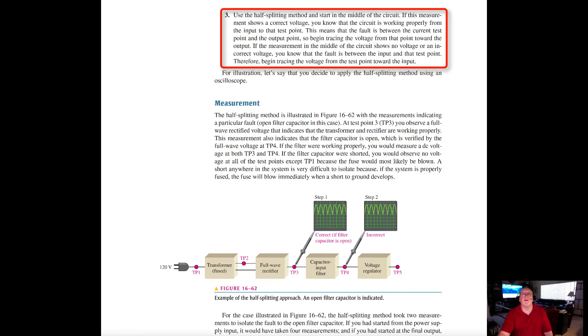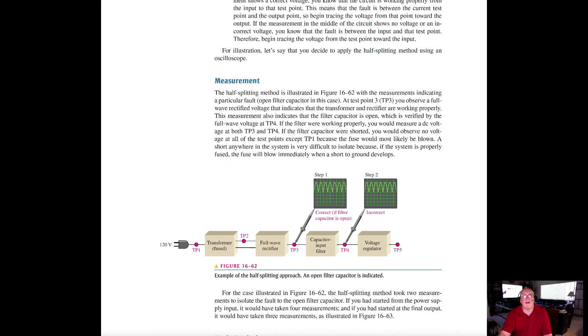Step 3: use the half splitting method and start in the middle of the circuit. If this measurement shows a correct voltage, you know that the circuit is working properly from the input to that test point. This means that the fault is between the current test point and the output point. Begin tracing the voltage from that point toward the output. If the measurement in the middle of the circuit shows no voltage or an incorrect voltage, you know the fault is between the input and the test point. Therefore, begin tracing the voltage from the test point toward the input.